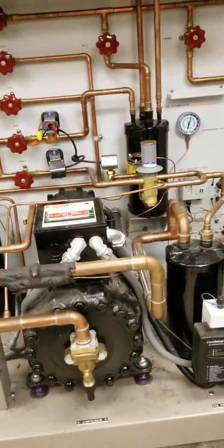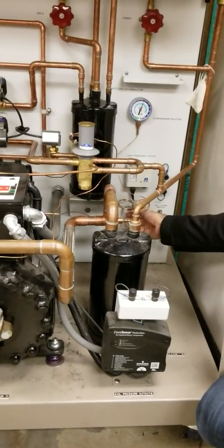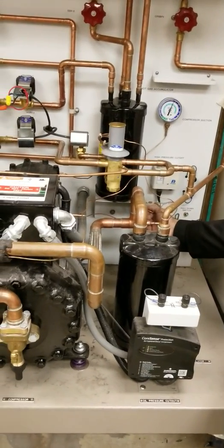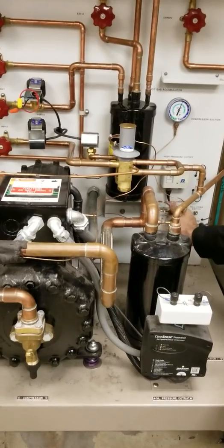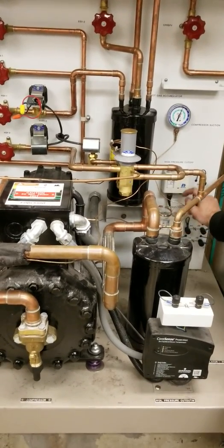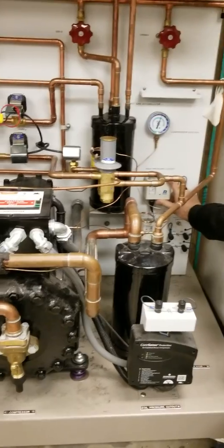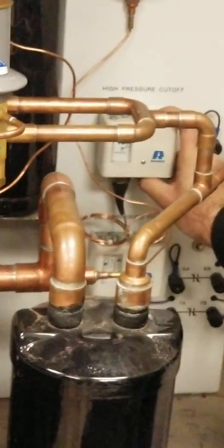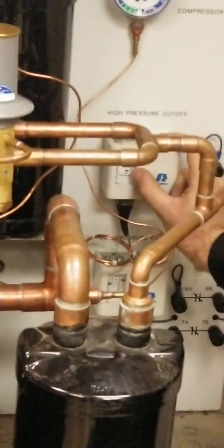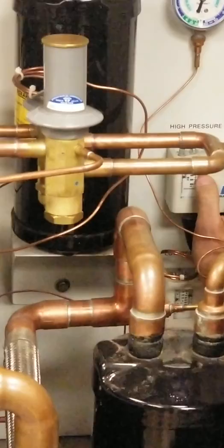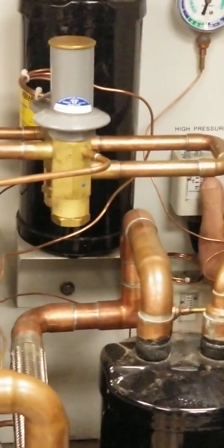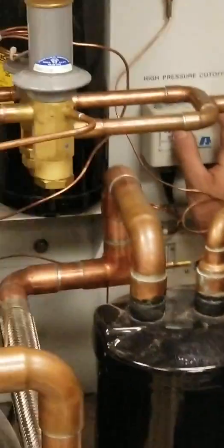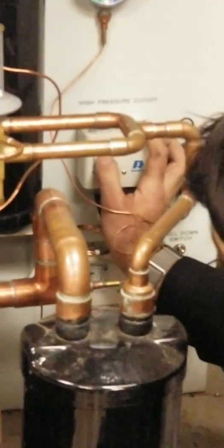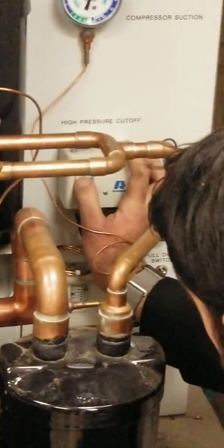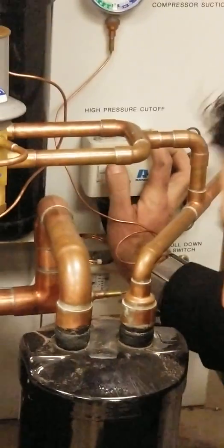So here we have a high pressure cutout. This is just tapped in over to our high side before our metering device after our compressor. And if we ever hit excessive pressure, if it gets too high, this cutout is going to kill our operation. It's going to break your line voltage, and it has an offset. So let's say right now it's set at just about 200. If this thing gets up to 200 psi, it's going to turn it off, and it's not going to let it turn back on until the pressure decreases 40 psi.